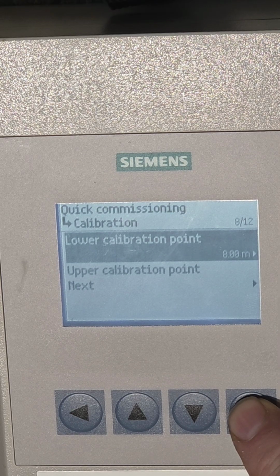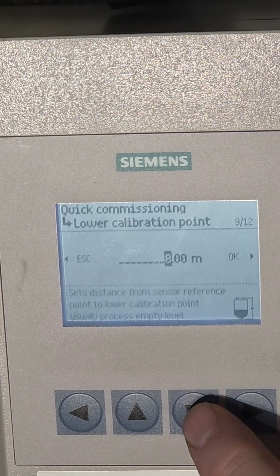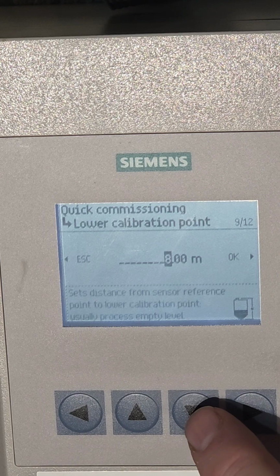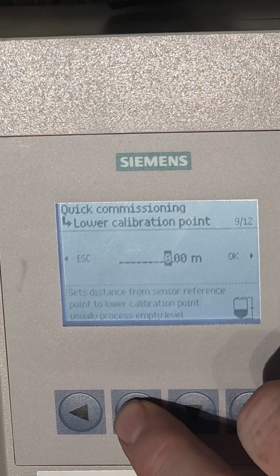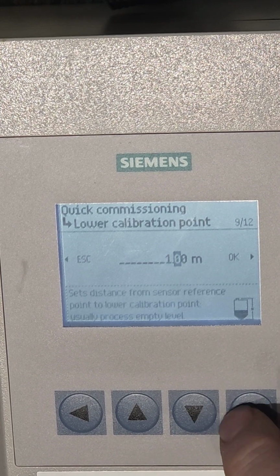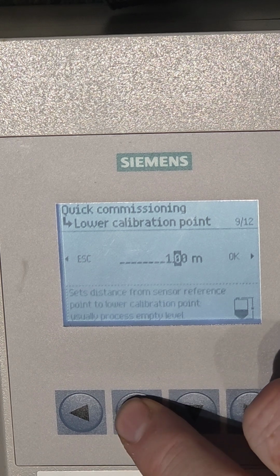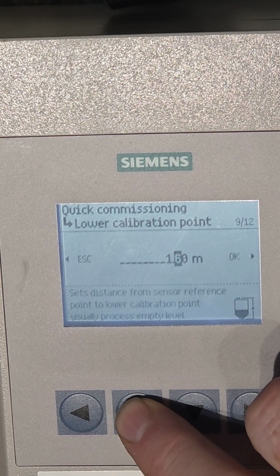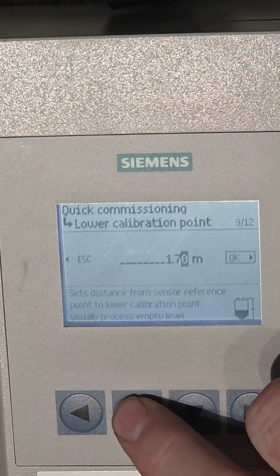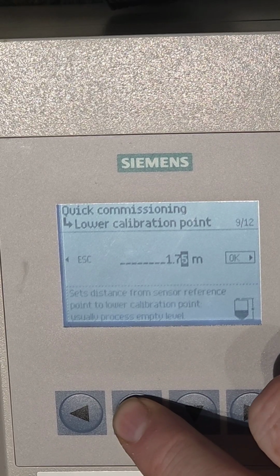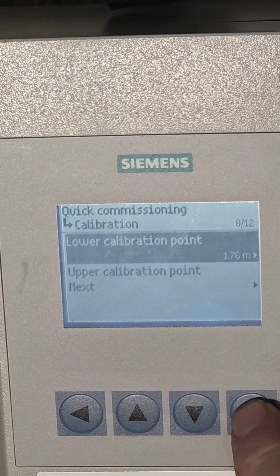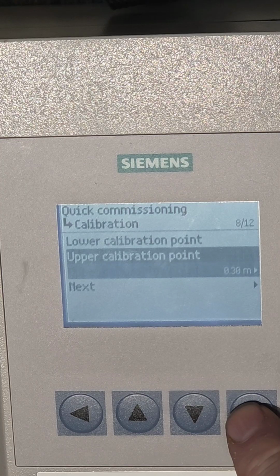The lower calibration point, that's the empty distance. The distance between the bottom of the ultrasonic head and the bottom of the tank. I want to change that to 1.76 meters. 1, 7, 6, 1.76.